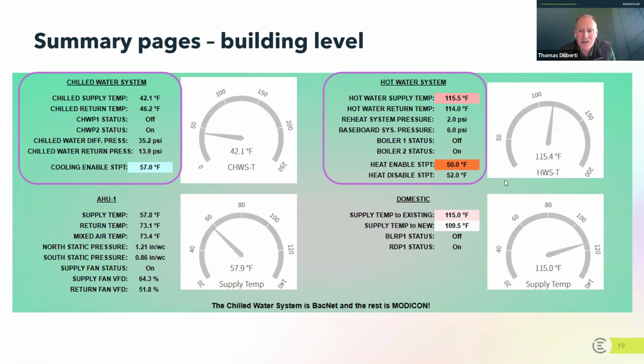As the outside temperature gets above 50, at 51, what's happening is you're between the enable and the disable set point. So the system's kind of coasting. But when you get over 52 degrees, now what it's saying is the system is going to turn itself off. So it's not going to allow the system to heat any longer. The logic being it's so warm outside, you don't need heat any longer. And as the temperature rises, you slide over here to this side. Now the cooling system is going to start up at 57 degrees.